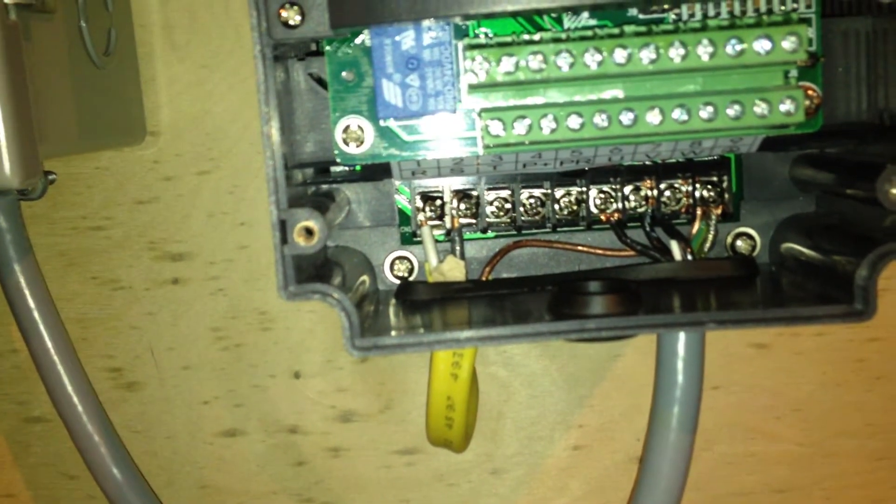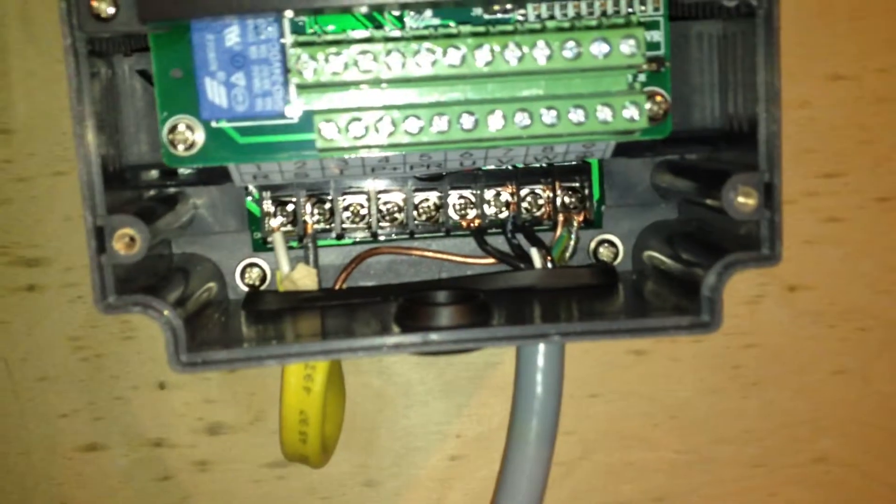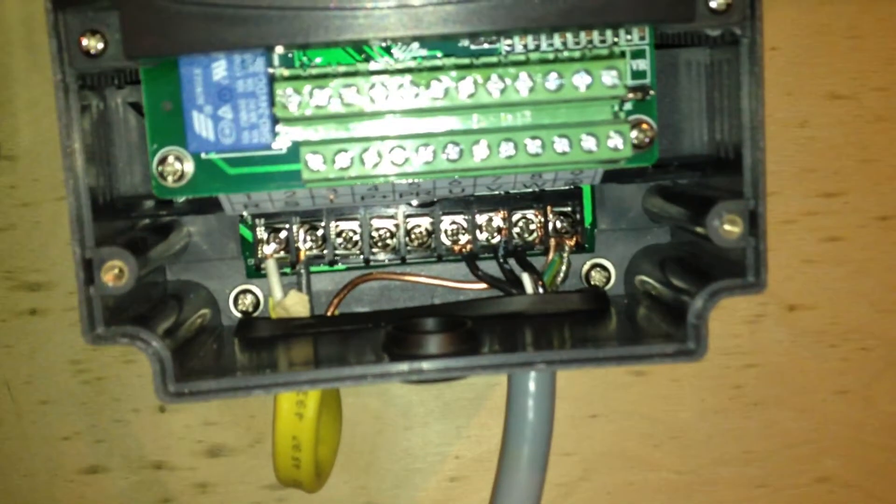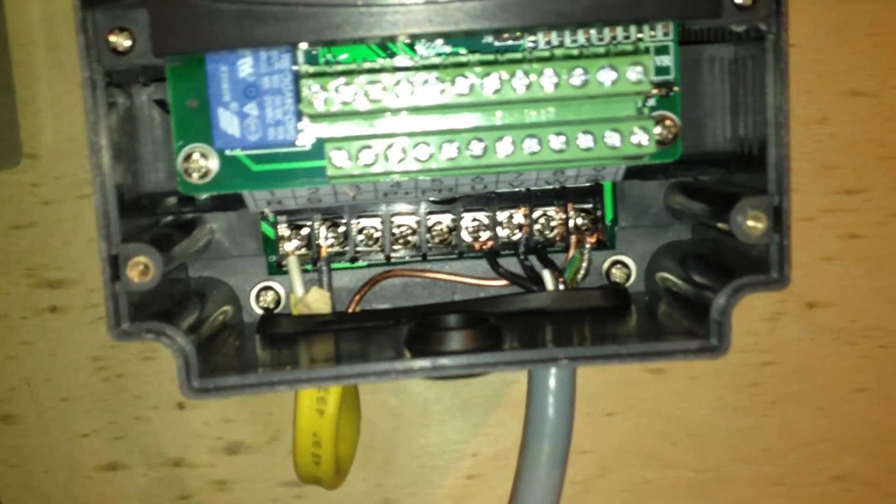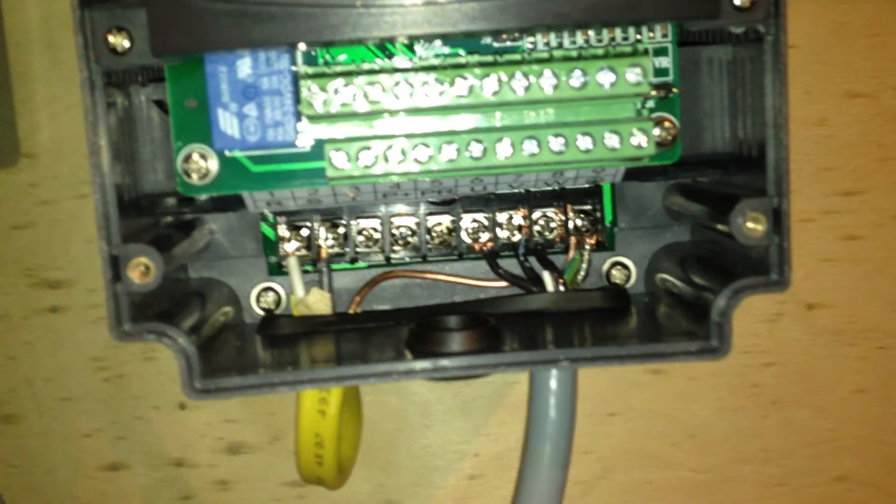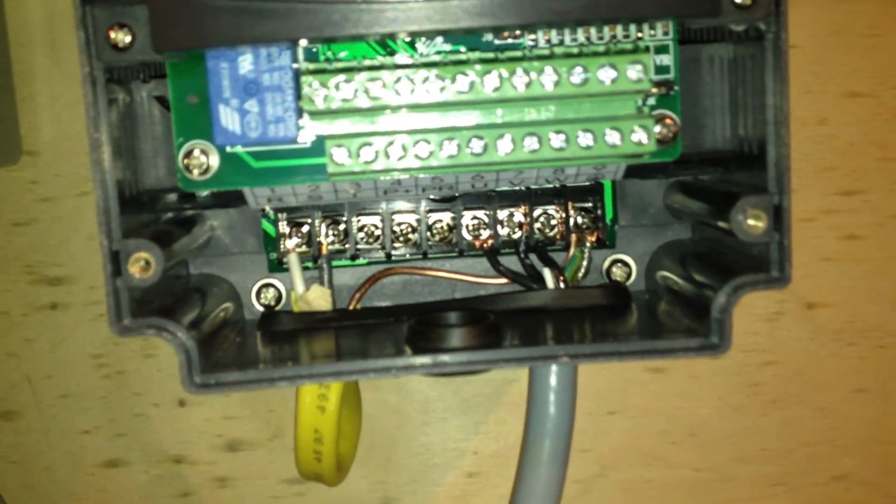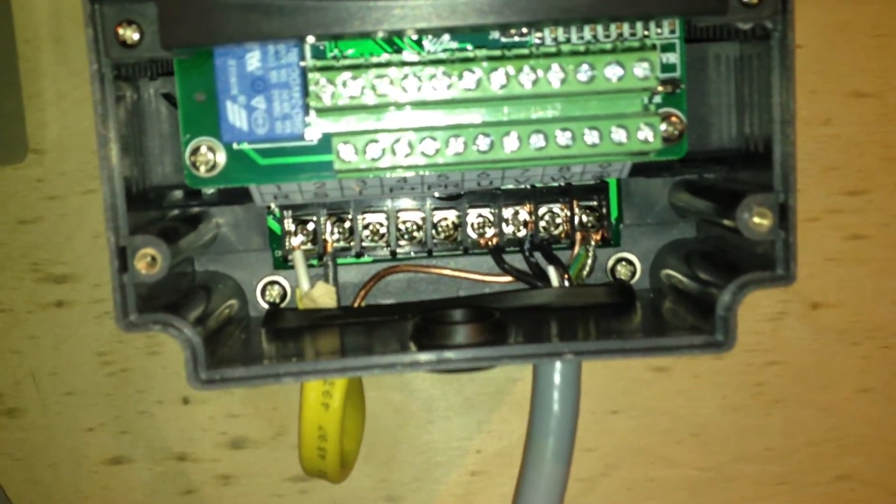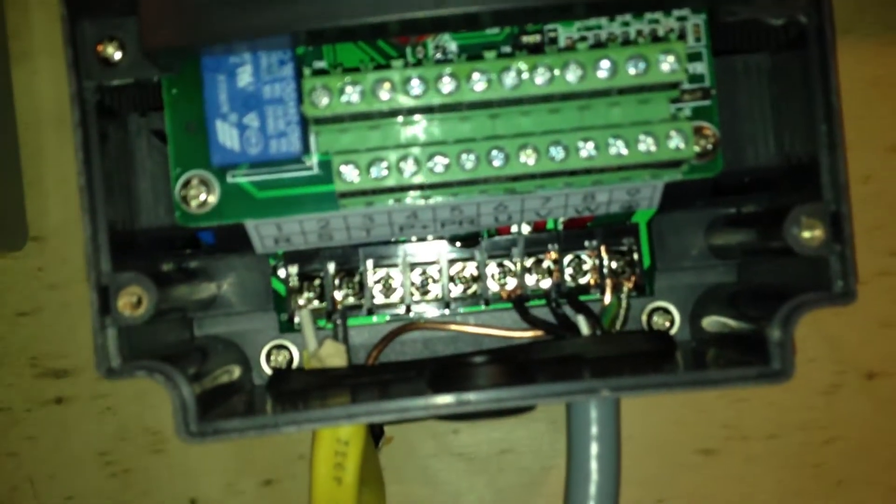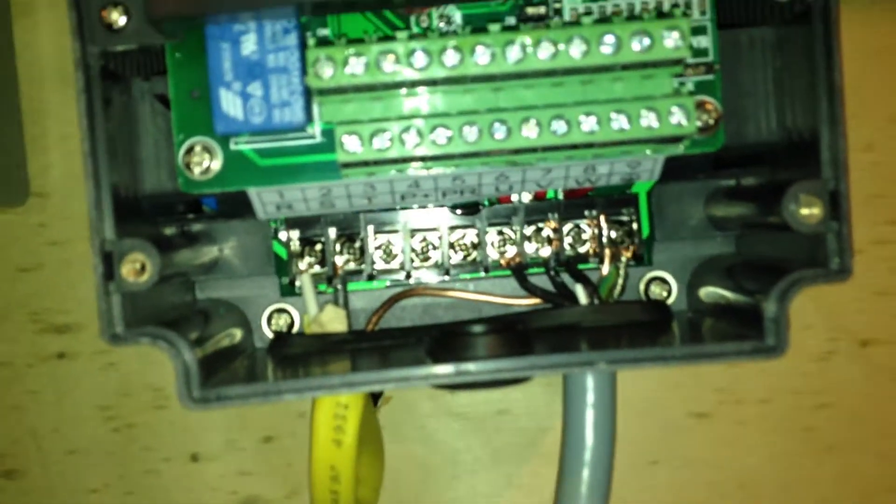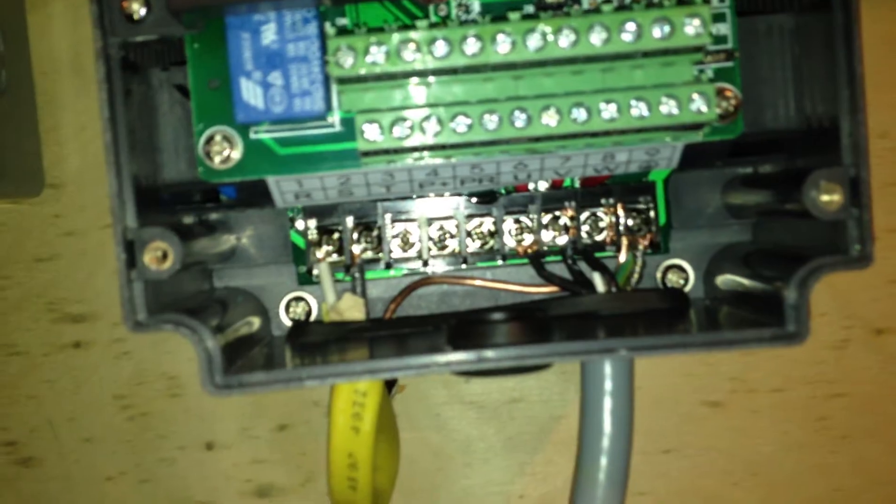Line is black, neutral is white, and ground running over to the other side. And then those three terminals next to the ground on the end there are labeled UVW, and those get sent out to the spindle.